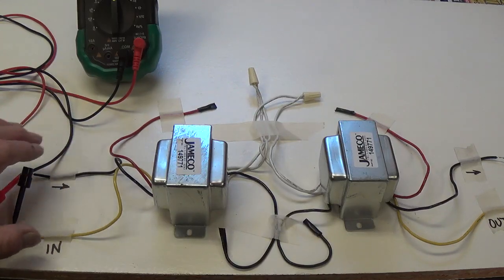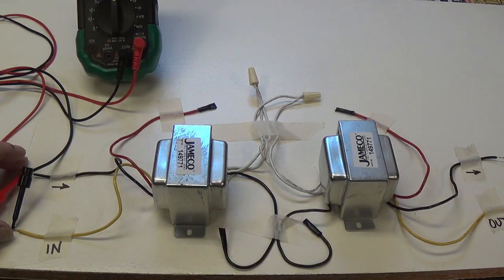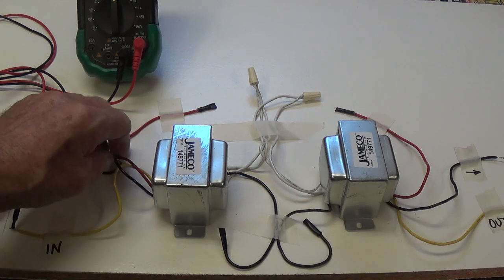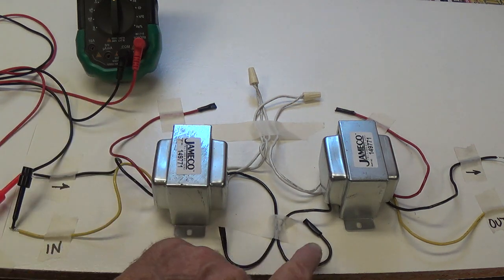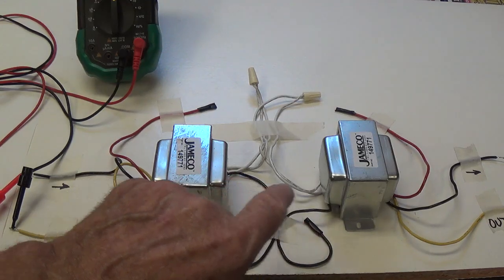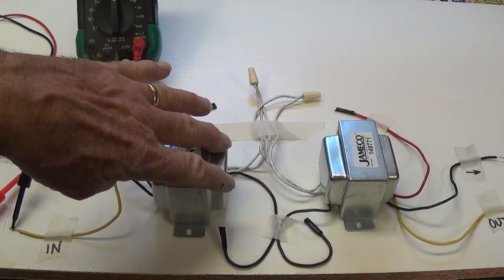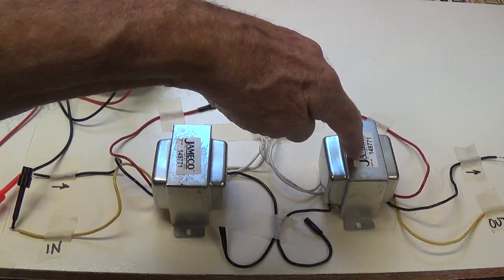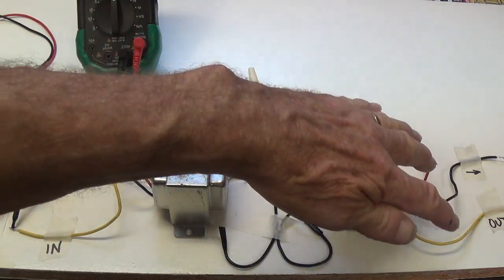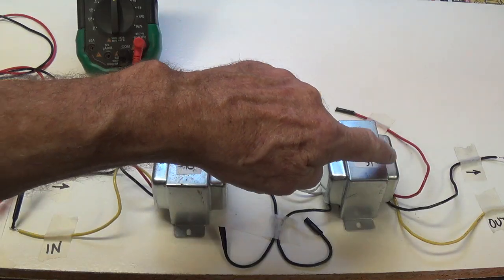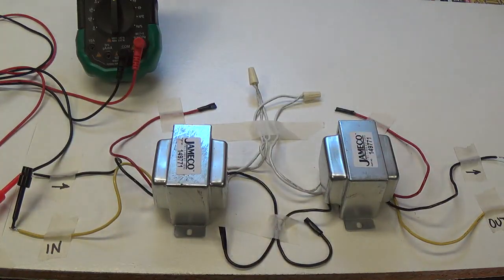Okay, using the color coding that was provided by the supplier of the transformers, I've connected them. Here the primary will be energized with 120 volts AC. I tied off the center taps and insulated the ends to keep them out of trouble. And we connected the 12 volt output from this one to the 12 volt input of the second transformer. And then we have the output voltage from the primary of this transformer.